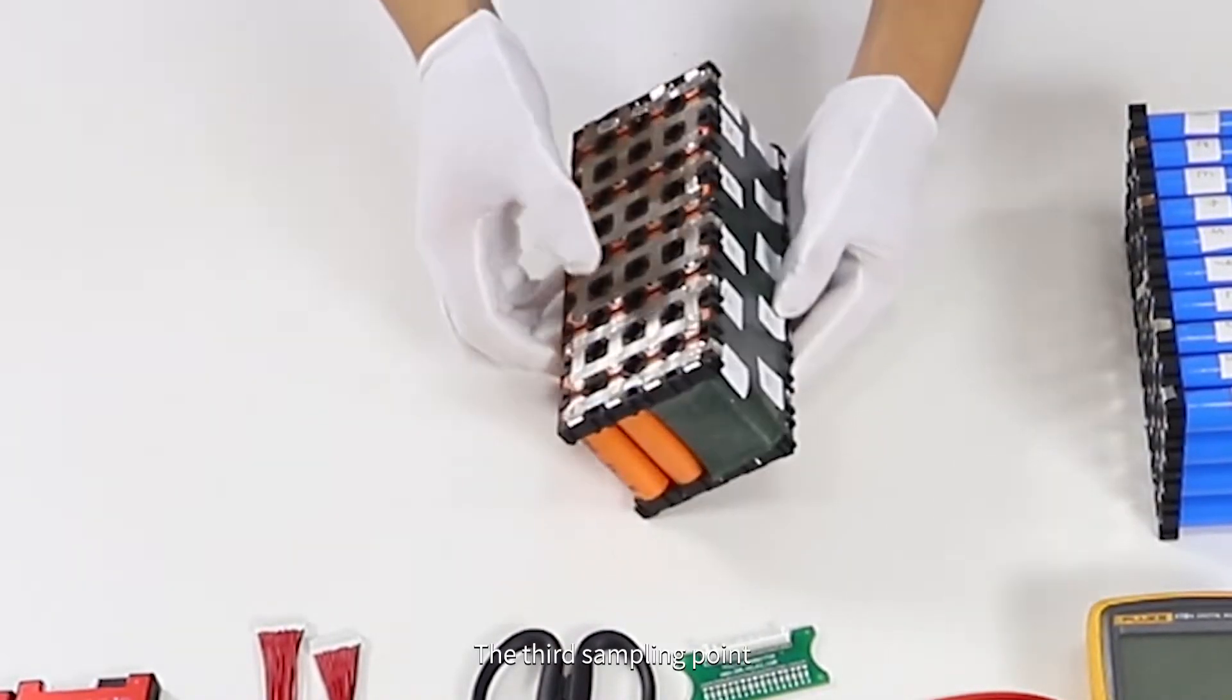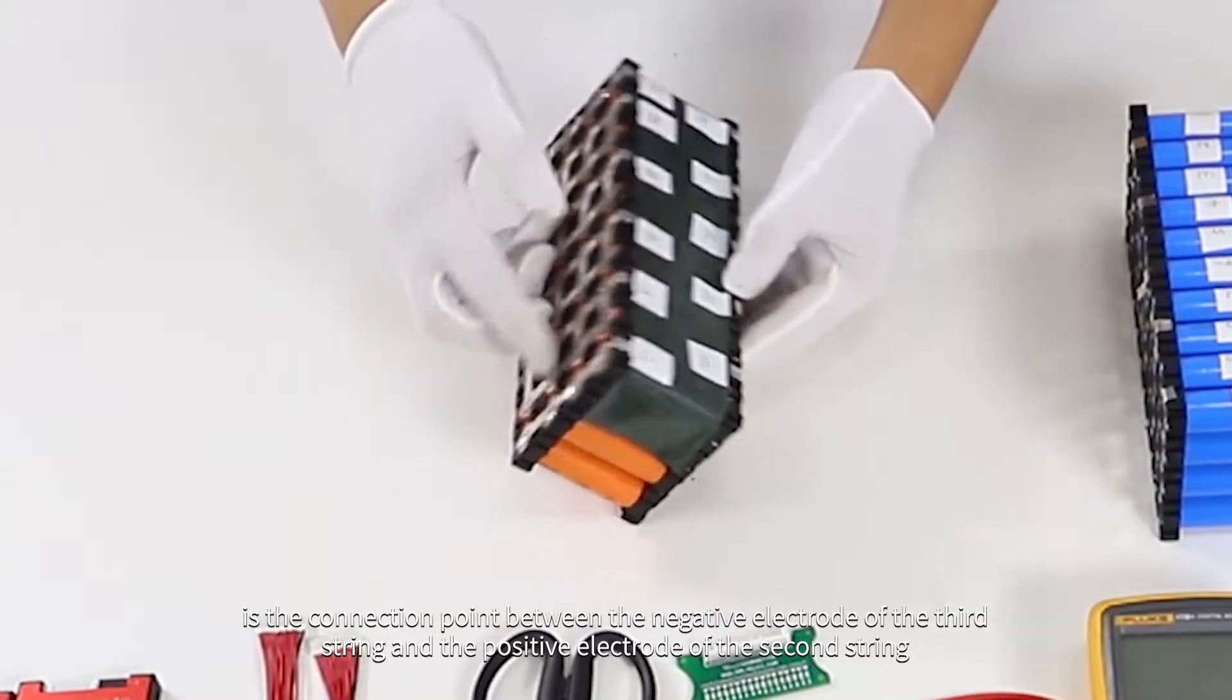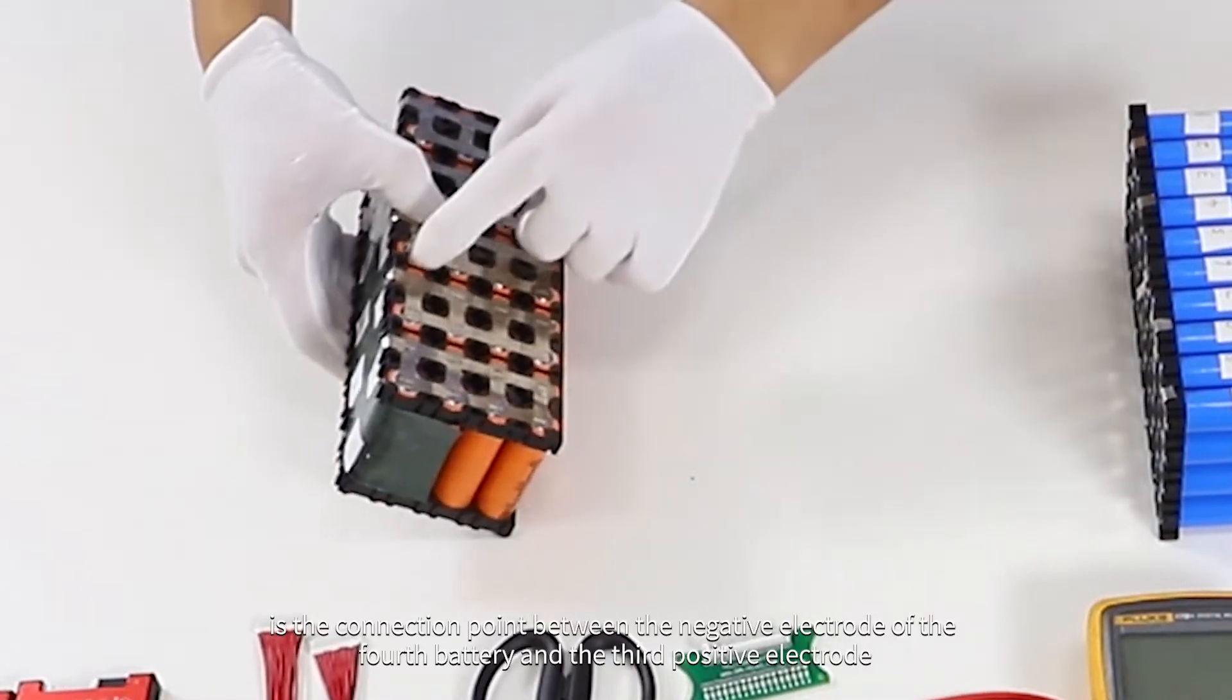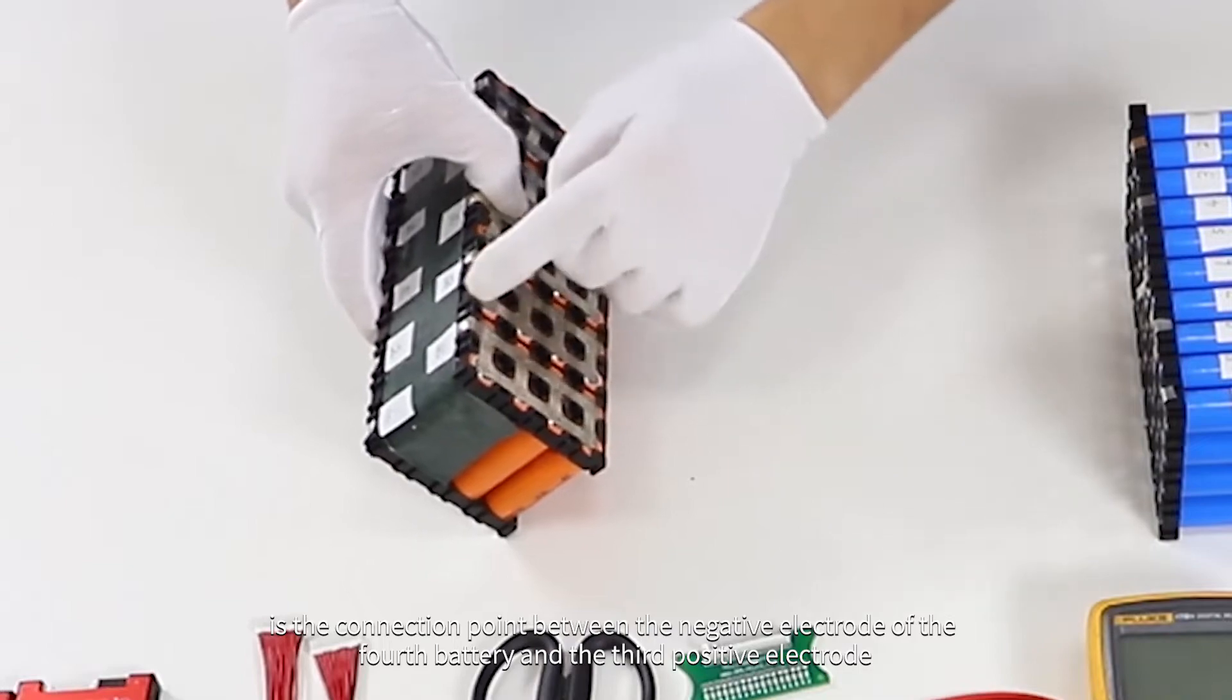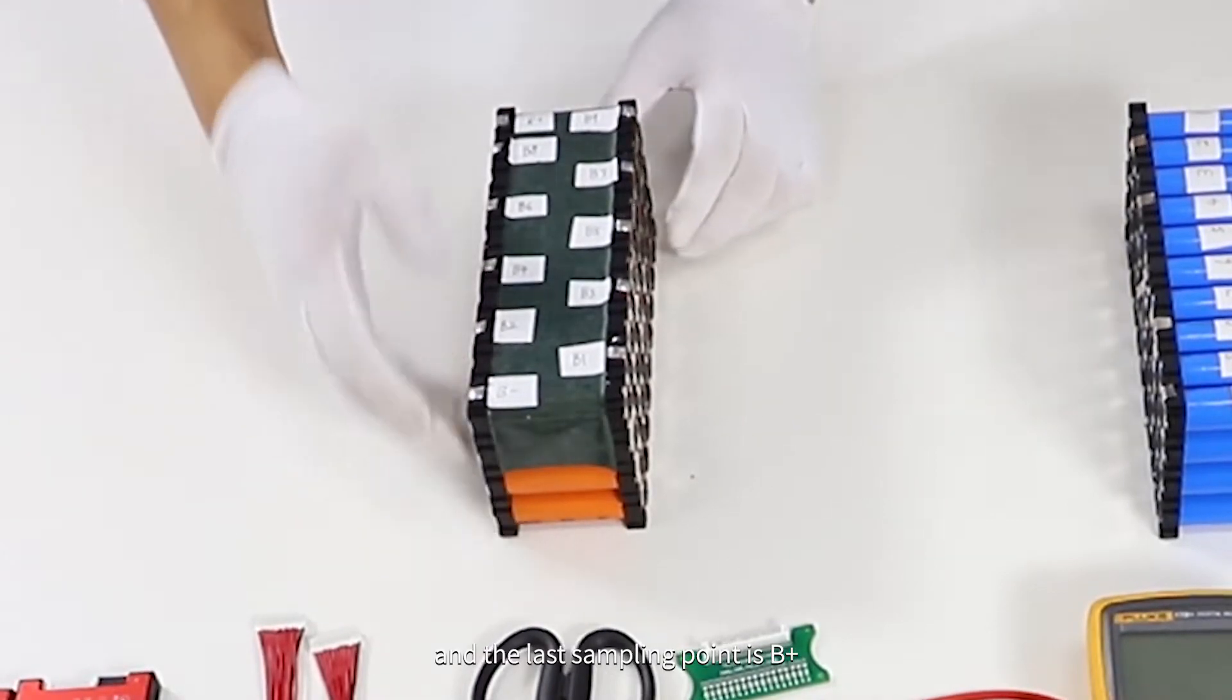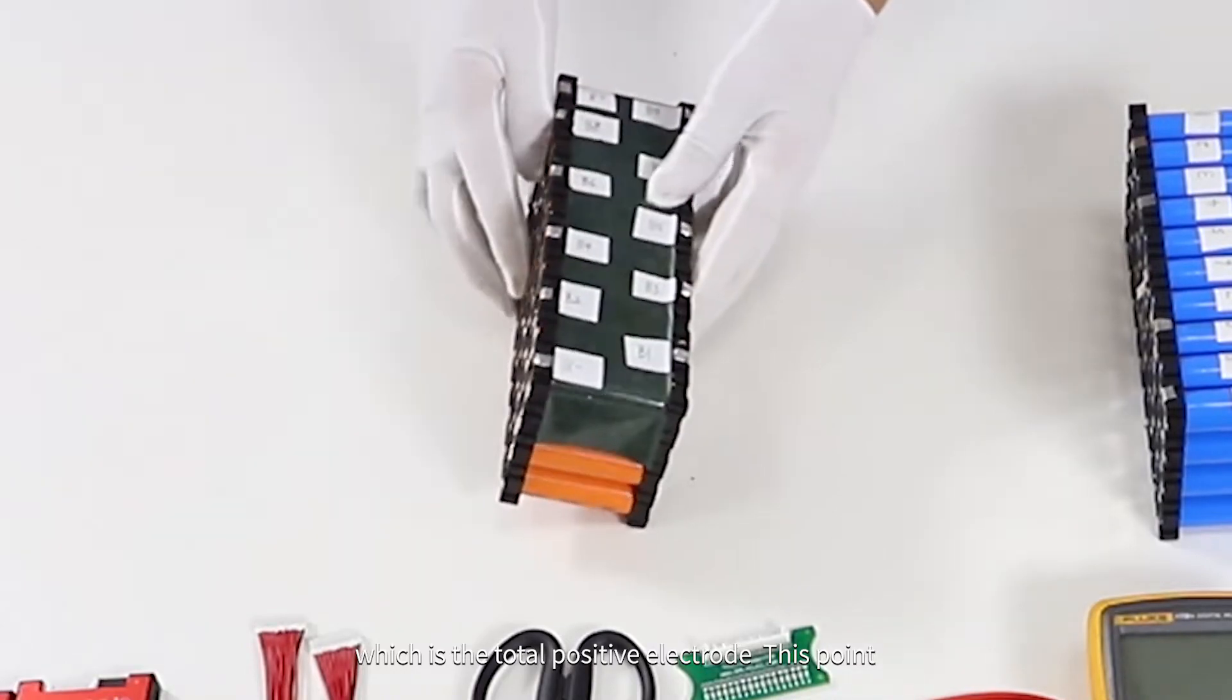The third sampling point is the connection point between the negative electrode of the third string and the positive electrode of the second string, marked as B2. The fourth sampling point is between the fourth battery negative and third positive, marked as B3. And so on, and the last sampling point is B+, which is the total positive electrode.